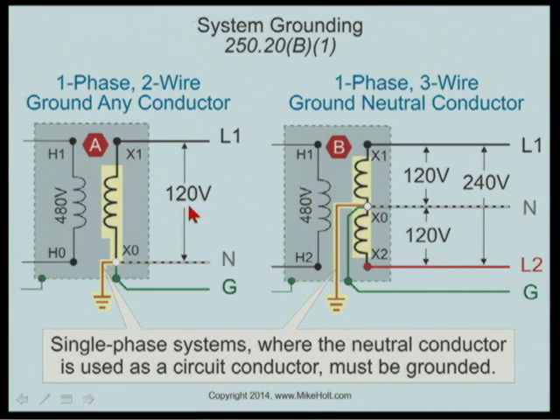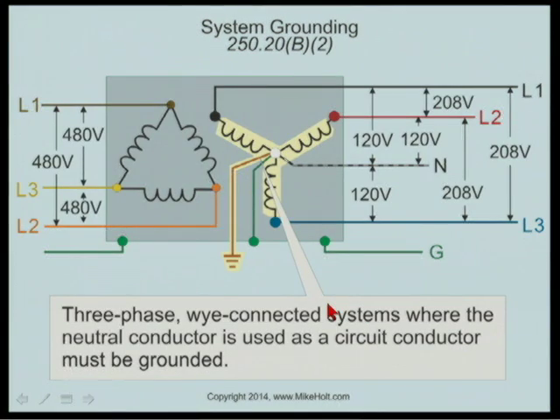Now, what systems are required to be grounded? Well, if you ever want a 120-volt circuit, then you have no choice. You have to ground one of the conductors. So if you have a 2-wire circuit that's 120 volts, line to neutral, then one phase has to be grounded. If you're going to have line to neutral 120 and 120, well, this is a typical 480 to 120/240, well then the center point is going to be grounded. If you have a Y system 120/208, since you have line to neutral loads, you have a neutral conductor in there, then you have to ground it. So let me just review this with you. You have ungrounded systems and you have grounded systems. An ungrounded system can be used in all these areas, except there are certain applications where you have to have a grounded system.